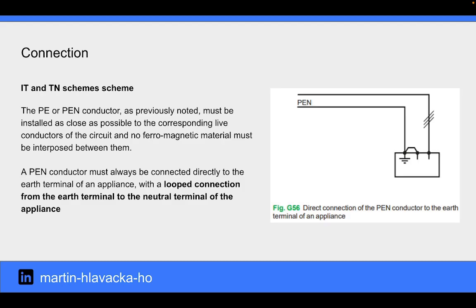In the IT and TN schemes, the PE or PEN conductor, as previously noted, must be installed as close as possible to the corresponding live conductors of the circuit, and no ferromagnetic material must be interposed between them. A PEN conductor must always be connected directly to the earth terminal of an appliance, with a looped connection from the earth terminal to the neutral terminal of the appliance.